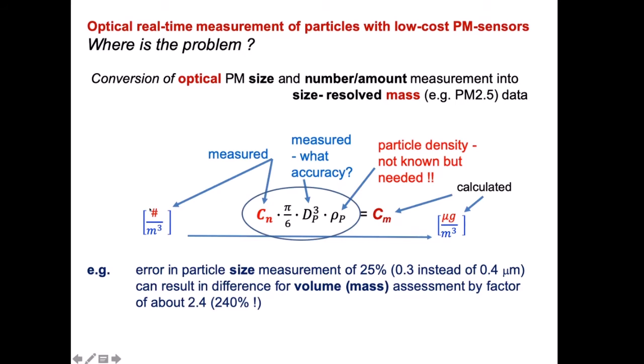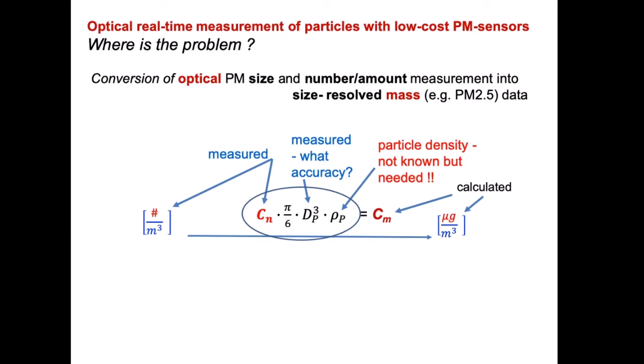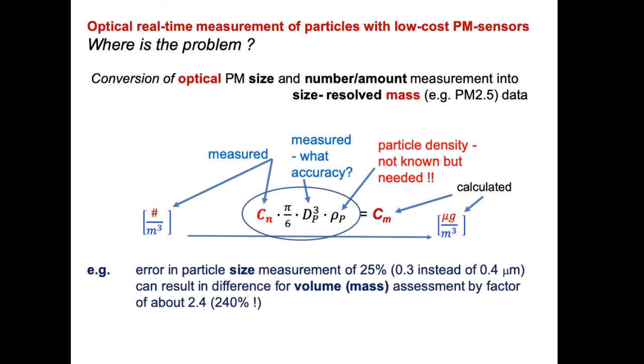From these two numbers, we try to infer mass concentrations in micrograms per cubic meter, but we don't know the particle density. So even if we say we know the average particle density, if we don't measure the size very accurately—say an error in size determination of 25%—this can result in a difference for volume or mass concentration of a factor of 2.4, which is 240%.